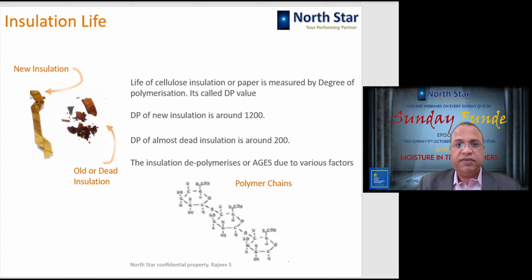So insulation life: if we look here, it is a new insulation, new kraft paper, typically a piece of conductor covering shown over here. When it becomes old, it becomes like this. So it is a dead insulation. It has no insulating properties, no electrical properties. Its life is over. Okay, so the life of cellulose insulation is measured with a term called degree of polymerization, or DP value. A brand new insulation will have a DP around 1200, and a dead insulation will have a DP of around 200.